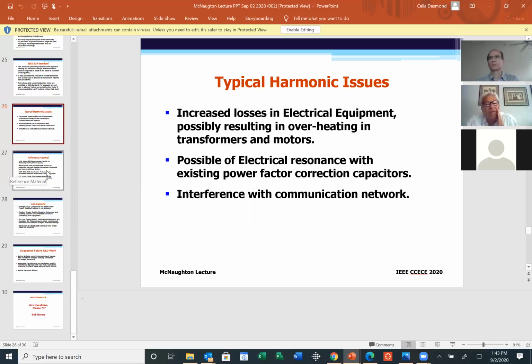The other impact of these harmonics is possible electrical resonance. Most plants will use power factor correction capacitors. Some of them might install drives that produce harmonics and inadvertently find fuse or capacitor failures, not knowing that in some cases you could have resonance. And the other one, of course, is interference with communication networks.